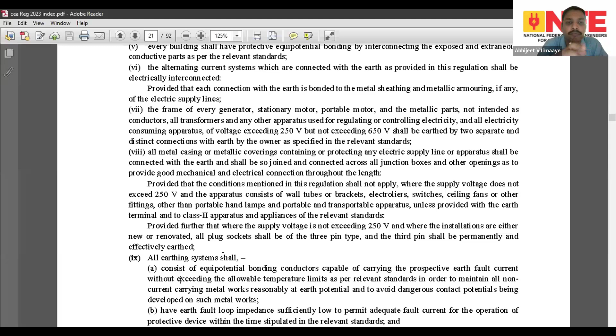Yes. So typically, when we talk about sub-regulation 9, it specifically talks about equipotential bonding. Now, what is equipotential bonding? I think there has been a lot of deliberation on it, but a very important part we need to understand about equipotential bonding is that there has to be one common earthing grid on the consumer premises. So you cannot have a different earthing grid for, let's say, electronics, or a different earthing grid for LAs. Everything has to be on a common earthing grid.